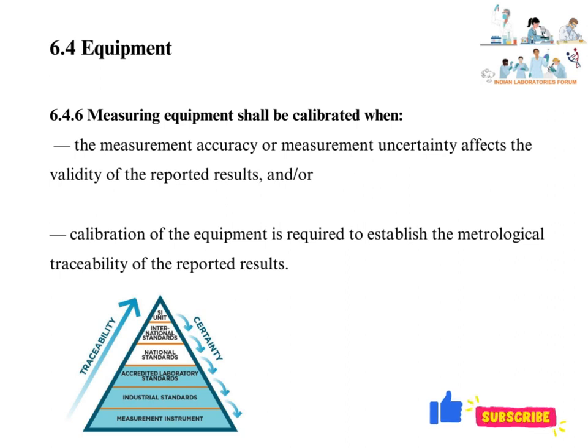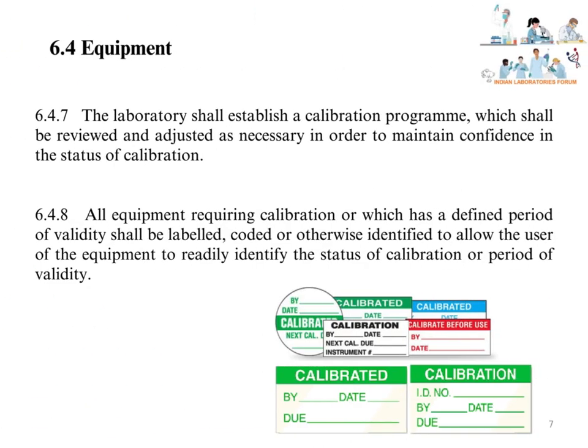Metrological traceability means establishment of an unbroken chain of calibrations to national or international standards. The laboratory shall establish a calibration program, which shall be reviewed and adjusted as necessary to maintain confidence in the status of calibration. The laboratory should have a documented calibration schedule reviewed periodically; if required, calibration frequency can be increased or decreased based on technical justification.